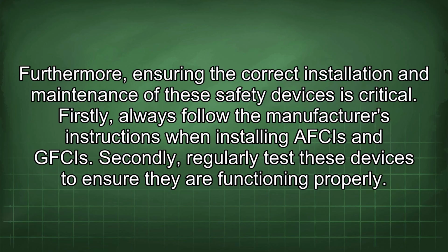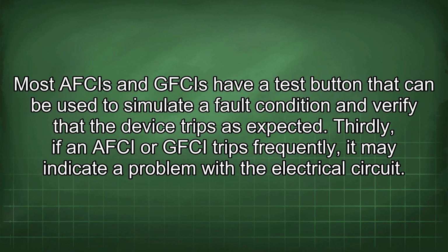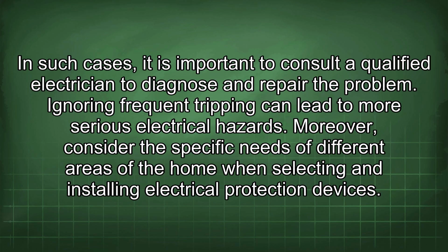Firstly, always follow the manufacturer's instructions when installing AFCIs and GFCIs. Secondly, regularly test these devices to ensure they are functioning properly. Most AFCIs and GFCIs have a test button that can be used to simulate a fault condition and verify that the device trips as expected. Thirdly, if an AFCI or GFCI trips frequently, it may indicate a problem with the electrical circuit. In such cases, it is important to consult a qualified electrician to diagnose and repair the problem. Ignoring frequent tripping can lead to more serious electrical hazards.